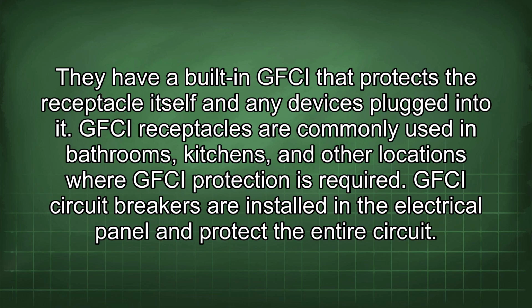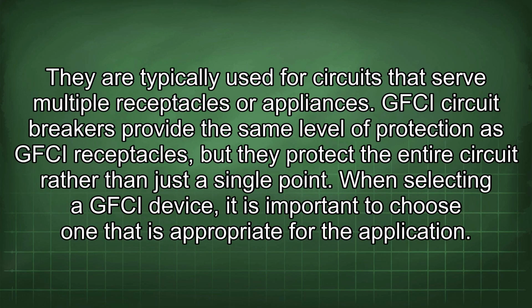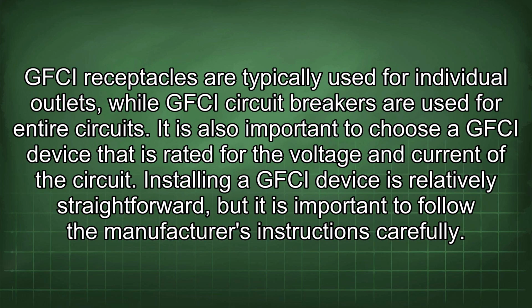GFCI circuit breakers are installed in the electrical panel and protect the entire circuit. They are typically used for circuits that serve multiple receptacles or appliances. GFCI circuit breakers provide the same level of protection as GFCI receptacles, but they protect the entire circuit rather than just a single point. When selecting a GFCI device, it is important to choose one that is appropriate for the application. GFCI receptacles are typically used for individual outlets, while GFCI circuit breakers are used for entire circuits.